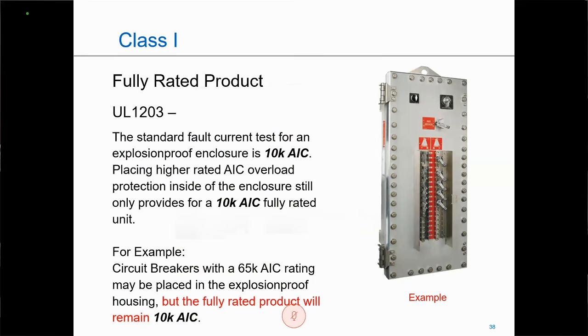In hazardous location areas, people will just sometimes put a higher rated piece of equipment in there, maybe a higher rated fuse, a higher rated circuit breaker, but the unit will still only be rated 10K. So it's going to be our weak link between the internal component and the enclosure. So the nameplate is still only going to say 10K. And the reason for that is that when the unit is tested for 1203, it's tested with a spark plug. That replicates the thermal explosion that you have with contacts opening and closing.